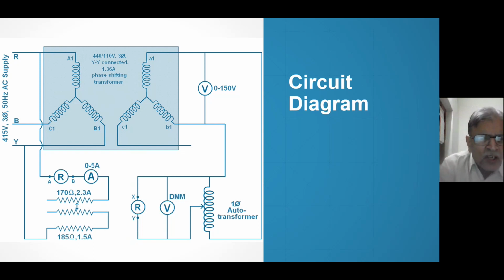But my capacity is 2.3 and 1.5 ampere, no problem. I'm not passing large current because that is not my wish. I am connecting the current coil of the relay at A and B, and connecting a 0 to 5 ampere ammeter to measure the current. I will use a 1 ampere relay, and pass 1 ampere through it, so rated current I will pass through the relay.